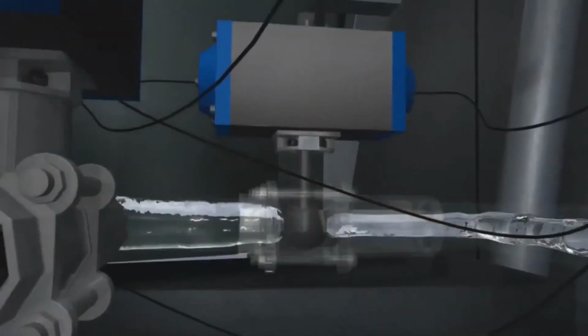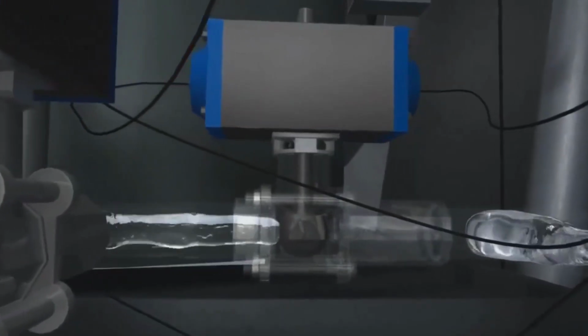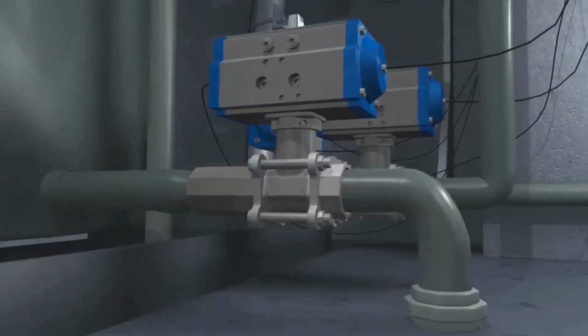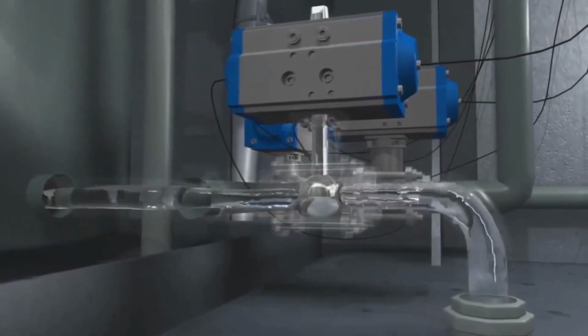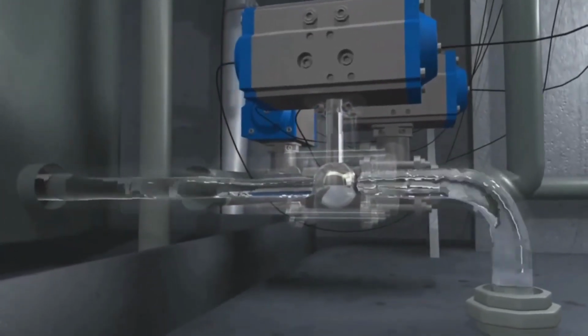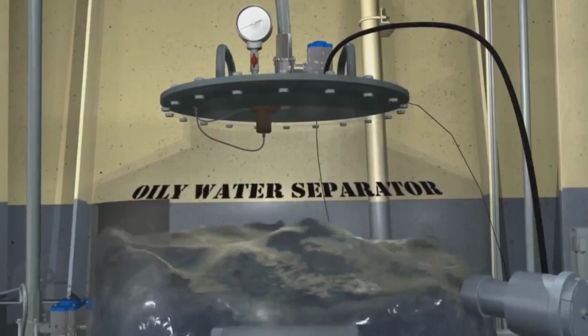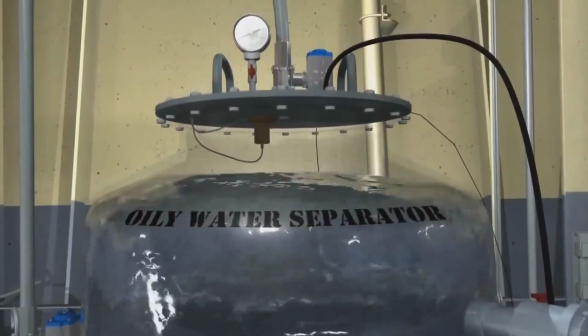3. The pneumatic overboard valve is shut to prevent any effluent from going overboard. 4. The pneumatic valve at the freshwater inlet is opened, which permits the freshwater to enter and flush out the oil from the main chamber to the separated bilge oil tank.